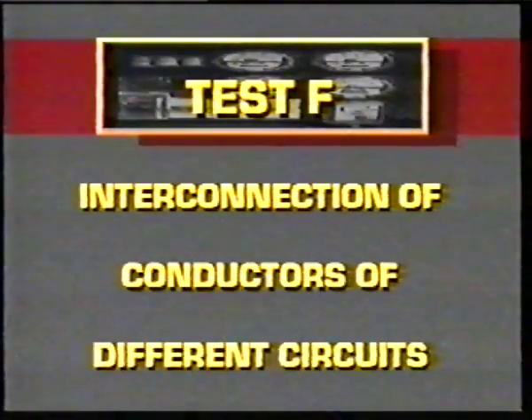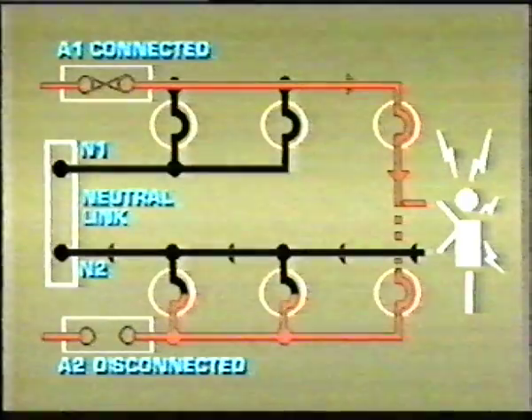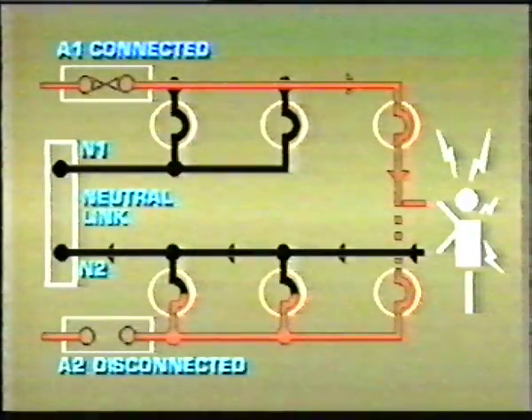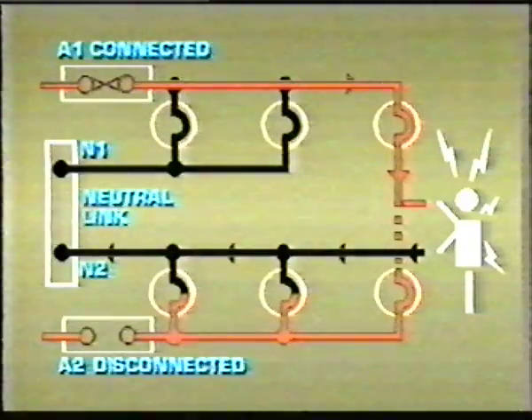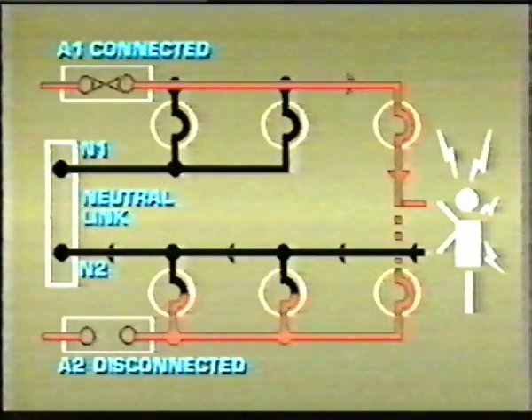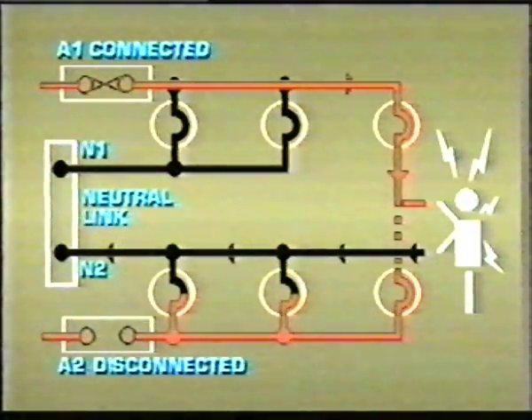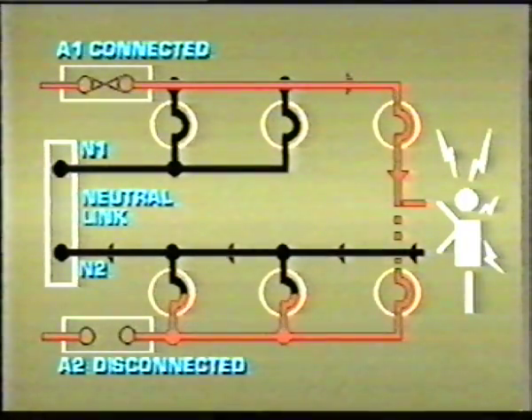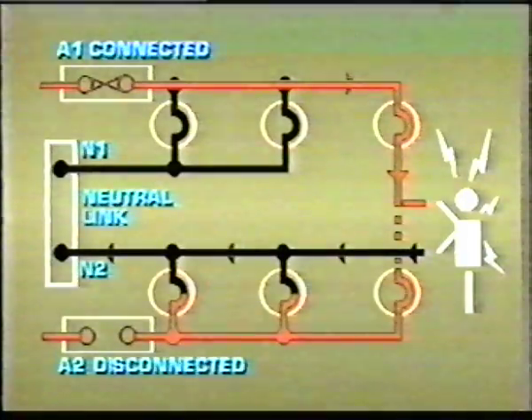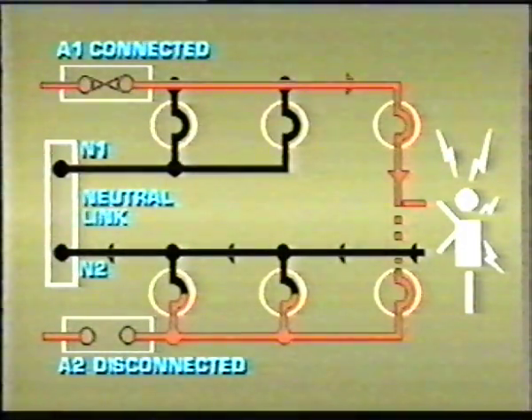Consider an installation where a live conductor from one circuit is used to connect equipment supplied from another circuit. Under normal operating conditions, it would appear to function correctly. However, a dangerous condition may be created when work is carried out on one of the apparently isolated circuits. Recognised methods of proving equipment or wiring to be dead may not be as effective, because in some instances, the dangerous condition will not become apparent until a neutral conductor is open-circuited.